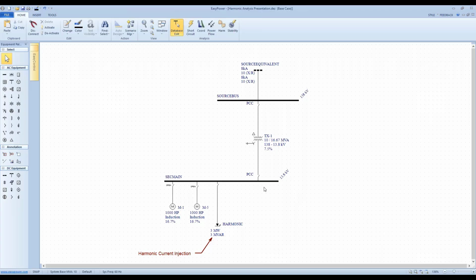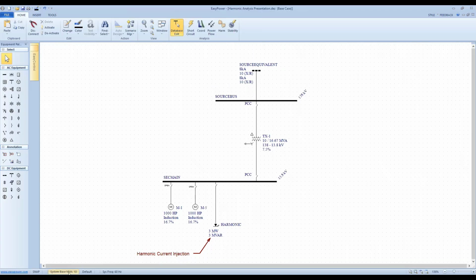and what does 1 per unit harmonic mean. So I will first say that you do have to have an understanding of the per unit system to be able to answer this question. And remember that per unit current is defined at each voltage level within the network. So at 138, there is a 1 per unit current. At the 13.8 kV level, there is a 1 per unit current. So since this is a 10 MVA network, this 13.8 kV system would have a 1 per unit value.